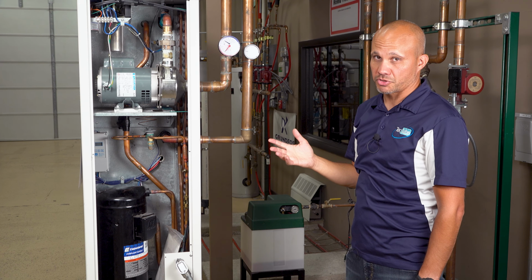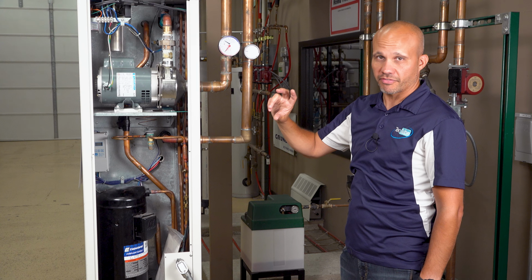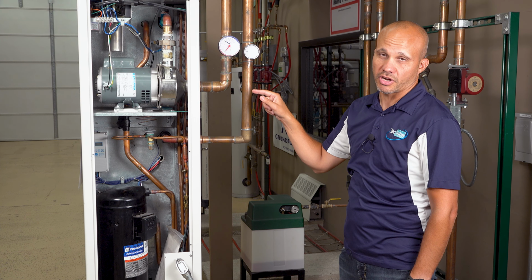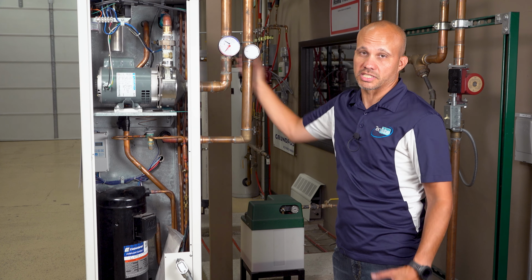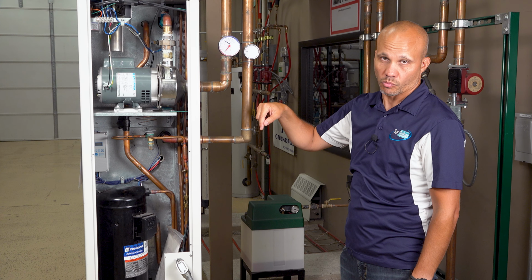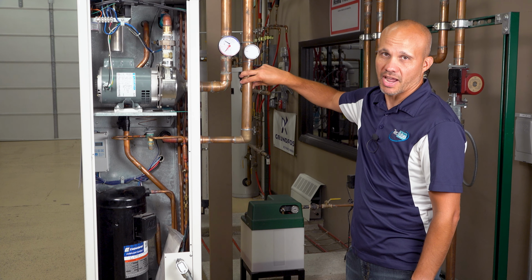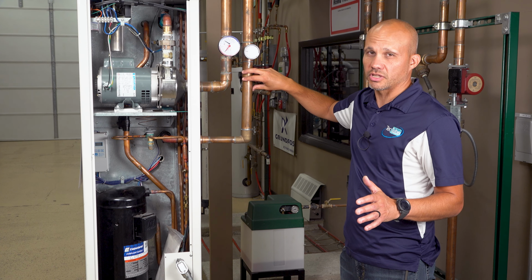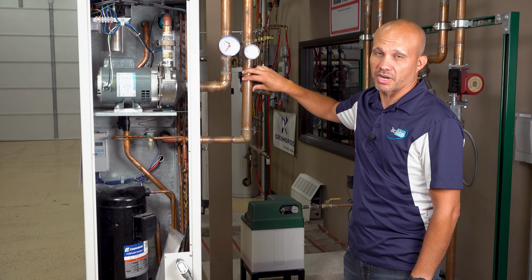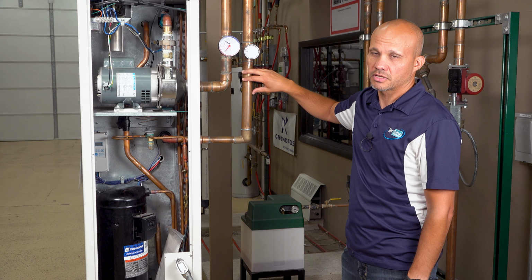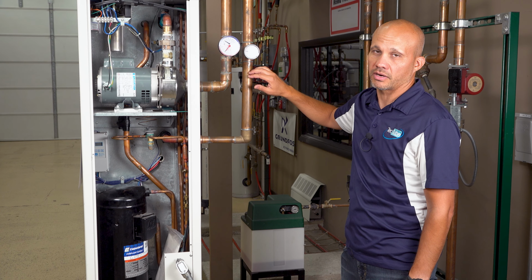When I have a heat pump chiller, what ends up happening is the reversing valve flips, just like it did in all the other heat pumps. And now, inside that refrigeration cycle, this coil out here is absorbing heat from the outdoors, and it's taking that heat and putting it into the water. So now coming out the supply pipe, I have hot water. Typically, not crazy hot, but like 110 to like 140 degrees, depending on the model of chiller, whereas a traditional boiler might be more like 180 degrees. So I can make hot water, but not crazy hot water. But it's enough to heat most buildings in most applications.